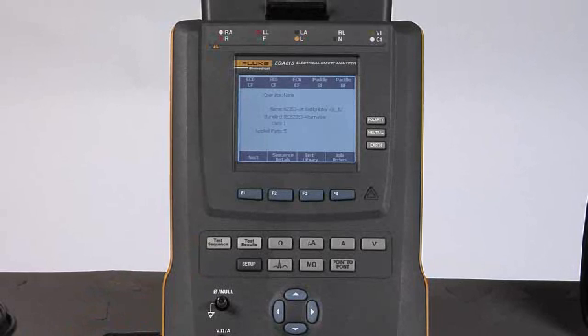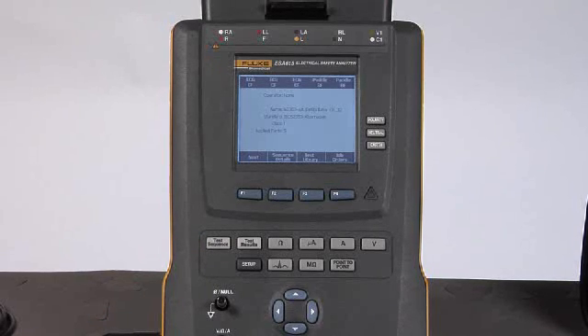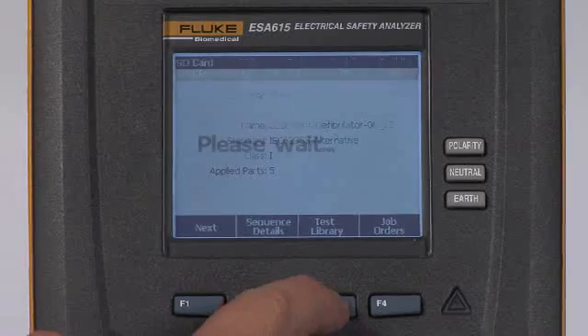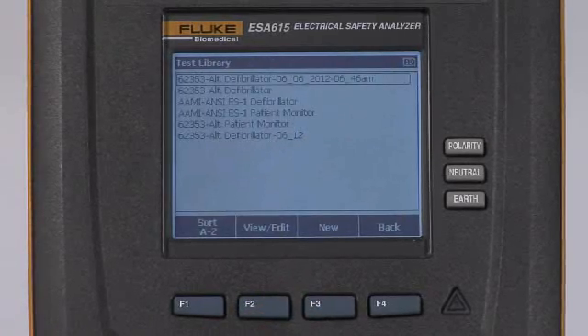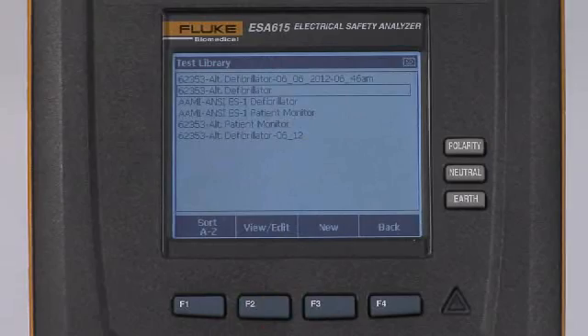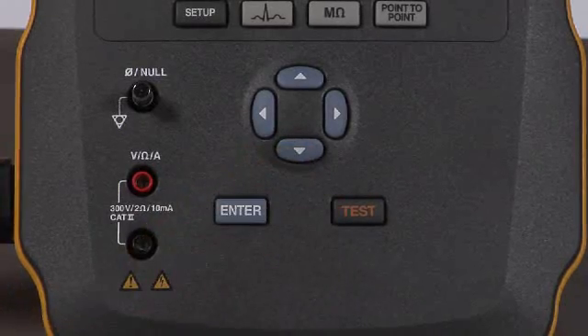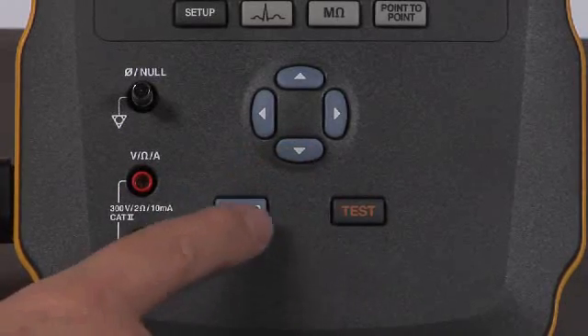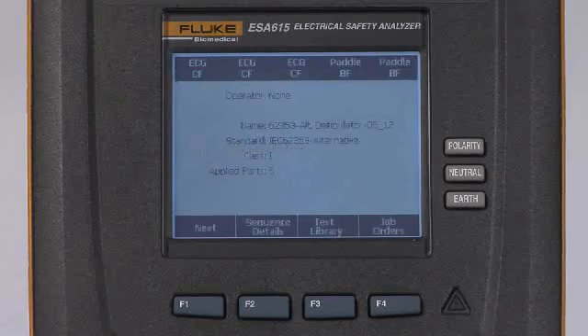If this test sequence is not the one that I want to run, I can easily select one from the test library, F3. And then I can use the navigation arrows and the enter button to select the test sequence that I wish to run.